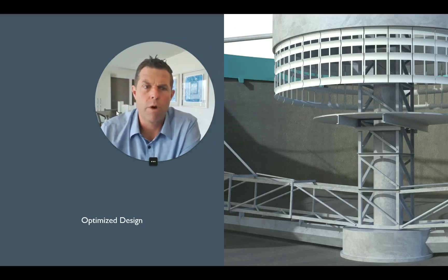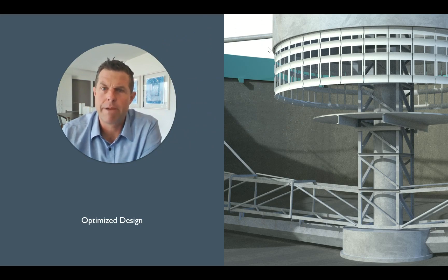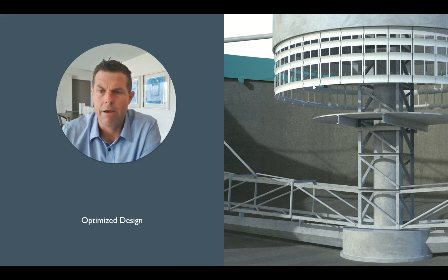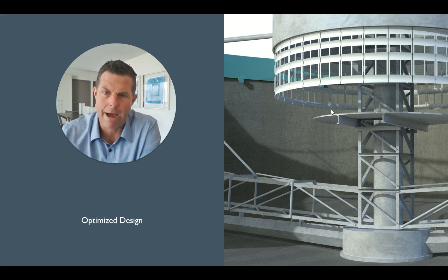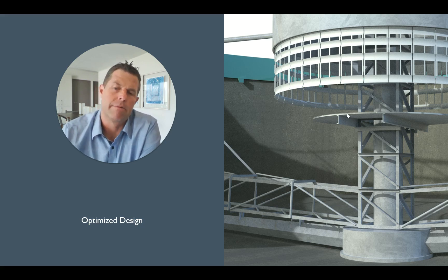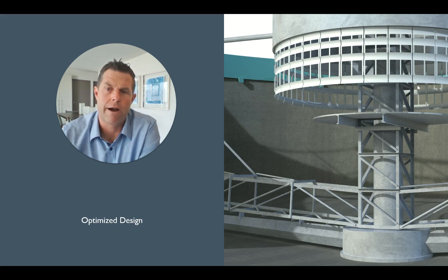This is a picture of what those improvements look like in this basin. We can see the existing floc well up top, where we are able to hang flocculation baffles around the perimeter. And here's that canopy baffle. As flows enter in, they bounce along this tank, are directed down, and then any downward velocity is cut off with this canopy baffle. That's how we were able to get such high performance in circular clarifiers — a combination of these two different systems.